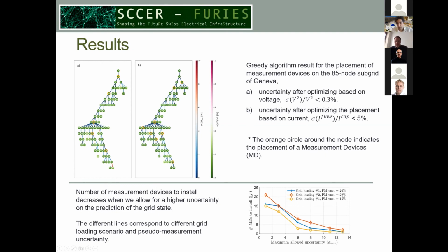We considered 2 cases, 20% or 50% load forecast error; in the case of higher load forecast error, we need more devices, also under different loading scenarios of the whole network. The key trend is that the higher the desired observability, the higher the number of measurement devices needed in the network.